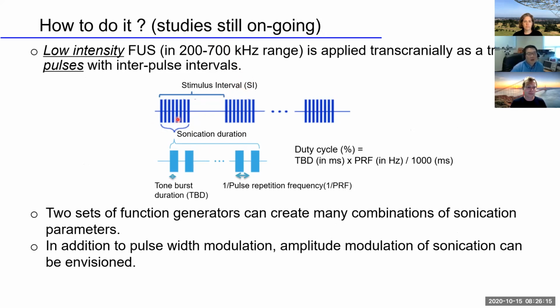First, low intensity focus ultrasound operating in the range of 200 to 700 kilohertz is applied transcranially as a train of pulses. You start with a specific tone burst, which is on the order of a millisecond or so. Then you repeat this rapidly. The frequency of this pulse repetition, we call it pulse repetition frequency, PRF, together with tone burst duration determines the duty cycle of each sonication.